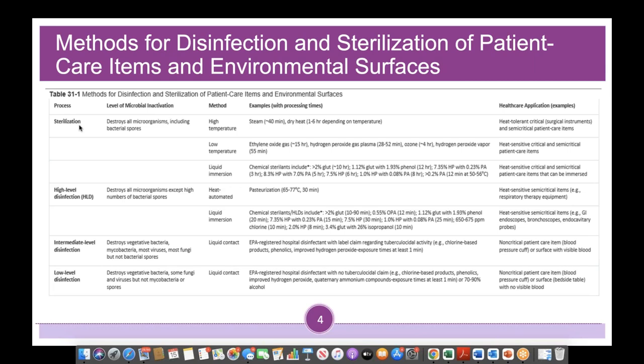So for our sterilization, it's going to destroy all microorganisms, including bacterial spores. High temp, we're thinking about steam, which is about 40 minutes, dry heat, 1 to 6 hours, depending on the temperature. These are going to be for heat-tolerant critical surgical instruments, and semi-critical patient care items, depending. That all depends on your facility, and the IFUs, the instructions for use.